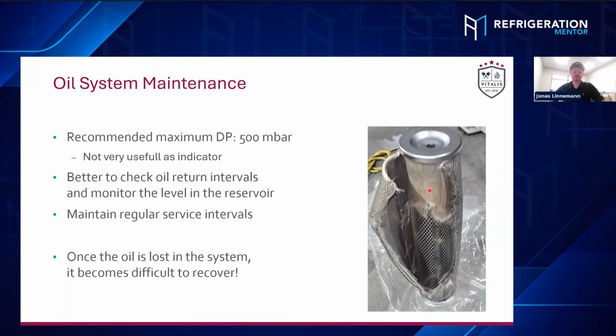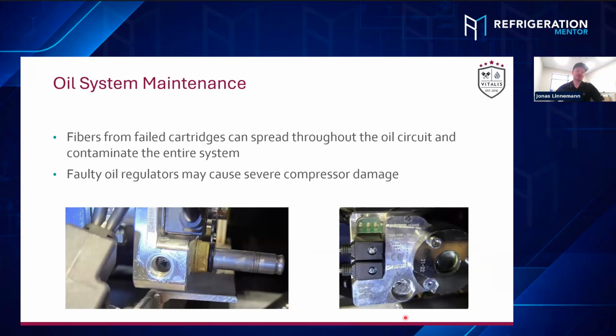Yeah, once such a cartridge is exploded, basically, and these little tiny fibers are traveling through the system, that's obviously nothing you want to see. But sometimes it causes even more damage. Here are some pictures of an oil level regulator, where basically all these fibers got stuck inside the valve seat. And then if the compressor is running, it can't refill enough oil. If the compressor is just on standby, there's a high risk of overfilling the oil level over time.